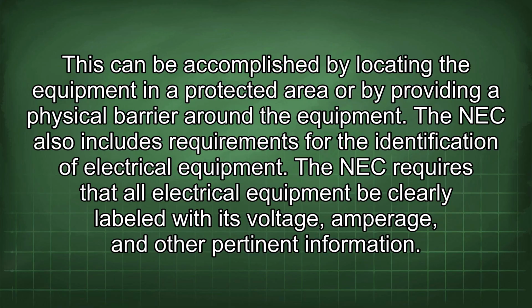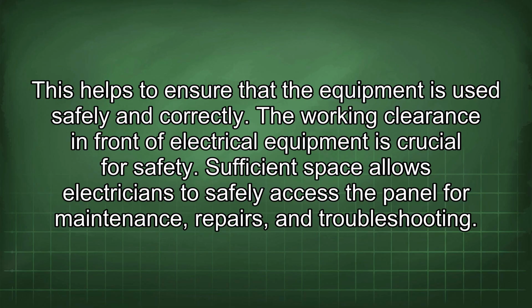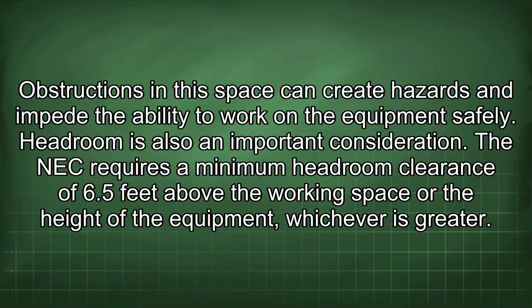This can be accomplished by locating the equipment in a protected area or by providing a physical barrier around the equipment. The NEC also includes requirements for the identification of electrical equipment. The NEC requires that all electrical equipment be clearly labeled with its voltage, amperage, and other pertinent information. This helps to ensure that the equipment is used safely and correctly. The working clearance in front of electrical equipment is crucial for safety. Sufficient space allows electricians to safely access the panel for maintenance, repairs, and troubleshooting. Obstructions in this space can create hazards and impede the ability to work on the equipment safely.